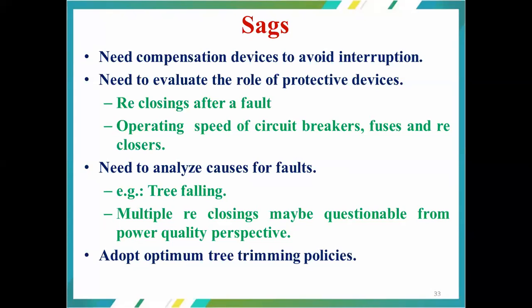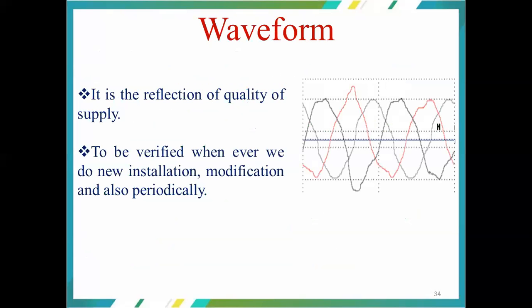We need to evaluate the role of protective devices, that is, reclosing after a fault, because sags may end up in the opening of circuit breakers, and again we are supposed to go for reclosing of the circuit breakers. The operating speed of circuit breakers, fuses and reclosers may be affected because of these sags. We need to analyze the causes of the faults, like a tree falling, or multiple reclosings, which may be questionable from a power quality perspective. And adopt optimum tree trimming policies. Again, we are supposed to maintain the distance between the power lines and nearby trees.